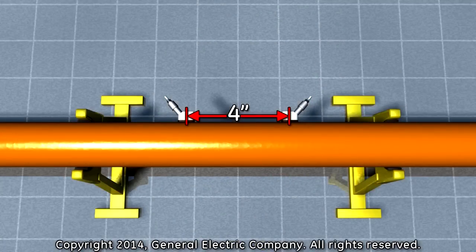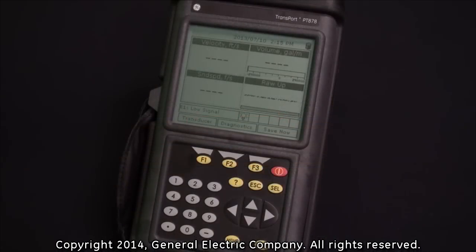The spacing is the distance between the transducers to be installed. Obtain the spacing and number of traverses from the PT-878 before installing the equipment.